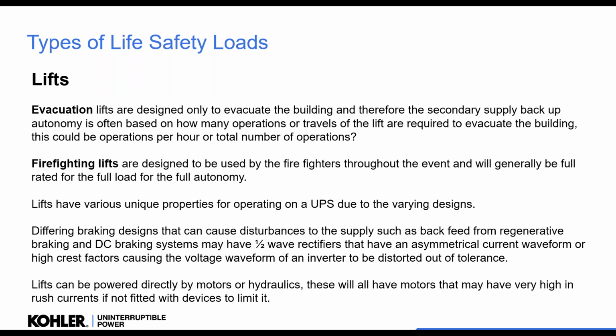The lifts, there are effectively two types of lifts for life safety. There's the evacuation lift and the firefighting lift. Now, the evacuation lift is purely there to evacuate the building and then not be used. So it's up to the designers to say how many operations of that lift are going to be required to evacuate the building. So we have the maximum autonomy of the UPS waiting for the lift to be used and the number of operations.